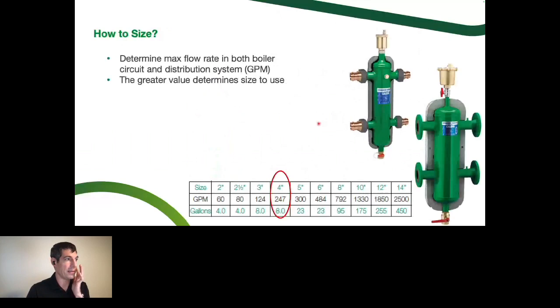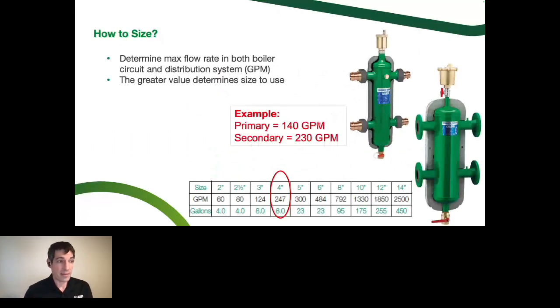So how do we size these things? Pretty easy compared to something like a point of distribution mixing valve for a plumbing system, where we have to know a lot of variables and a lot of things about the building. For this, we have to know what the higher flow rate is on the energy source side, the boiler, heat pump, or chiller side, or on the system side. So let's say in this example, the primary loop, we'll say it's on the left side, is 140 GPM max flow rate, and the secondary is 230.